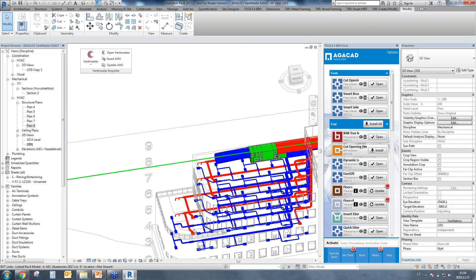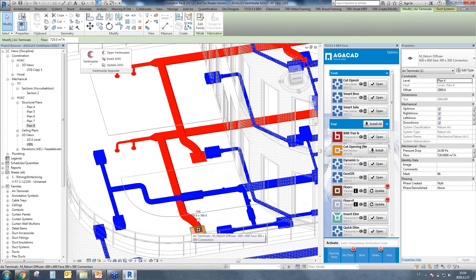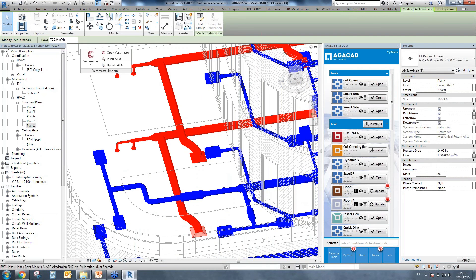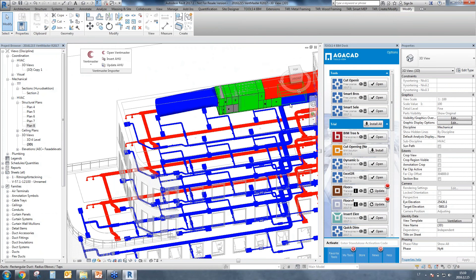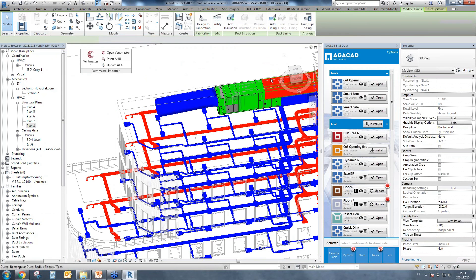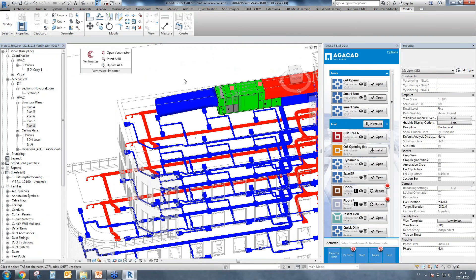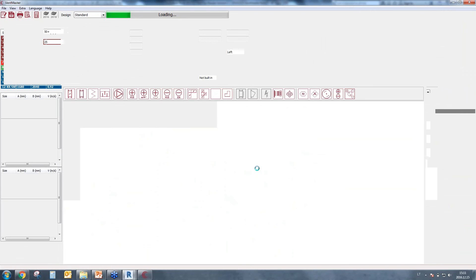Afterwards you just need to make some extra ductwork from it if needed. I just pick the duct, round one, and draw to another side. I have really nicely connected element. One more thing: what if we change some air flows in our system? Let's add 1000 cubic meters just to make a good idea for you. Everything was recalculated in Revit in the duct, so we have different air flows right now. We need to update our model because it still has something wrong here. We just click update button and we choose the family, and the Ventmaster software is opening again. It knows all the parameters from the project that was created before. Romana, could you lead my idea further please?